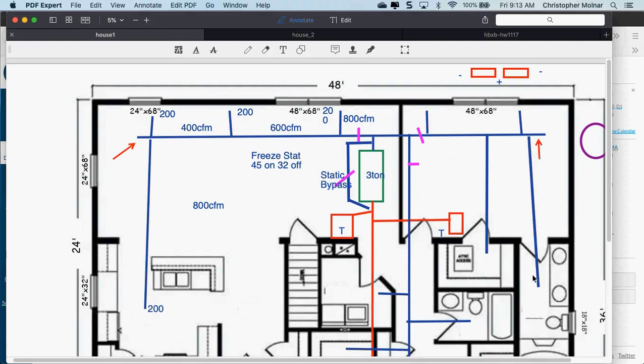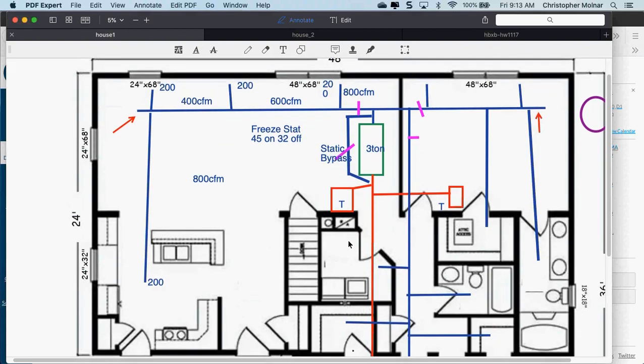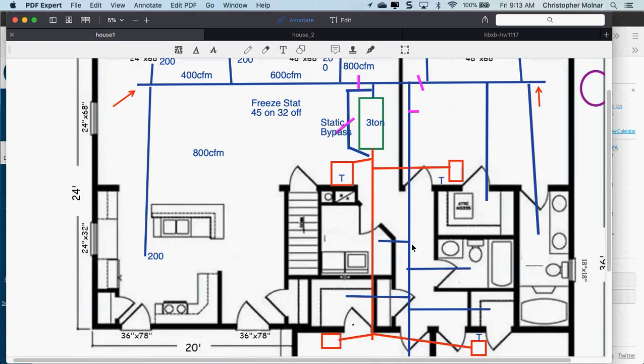The instructor clarifies: he didn't do a heat load on the example house — he just threw numbers in. You really don't want to deliver less than 25% of your air handler CFM to a zone. The air handler is only 600–620 CFM, so 190 CFM is just borderline. If you put in a two-stage condenser — one of the higher-end ones — the compressor could run on low speed and you'd be fine.